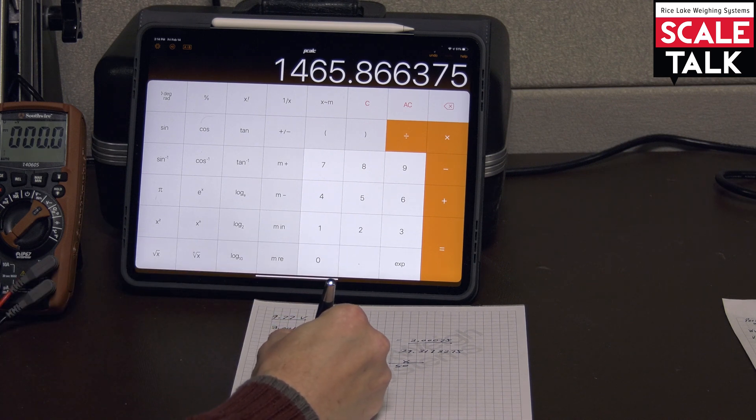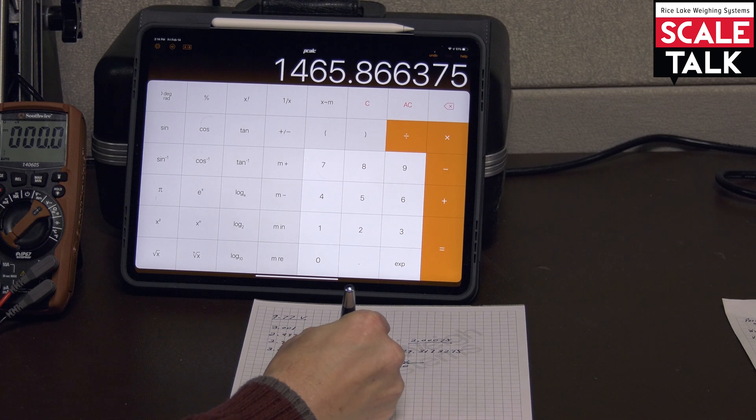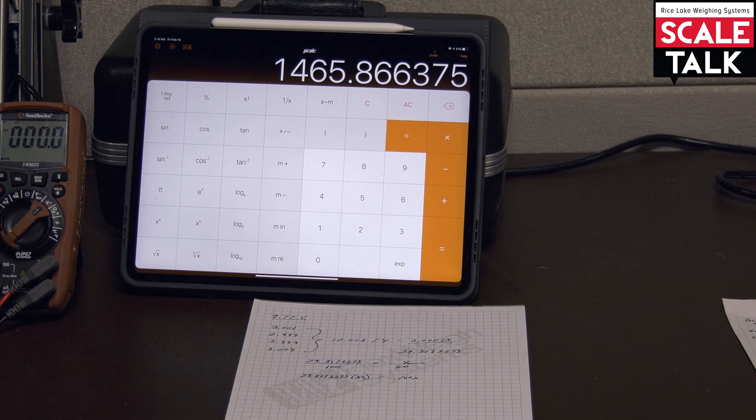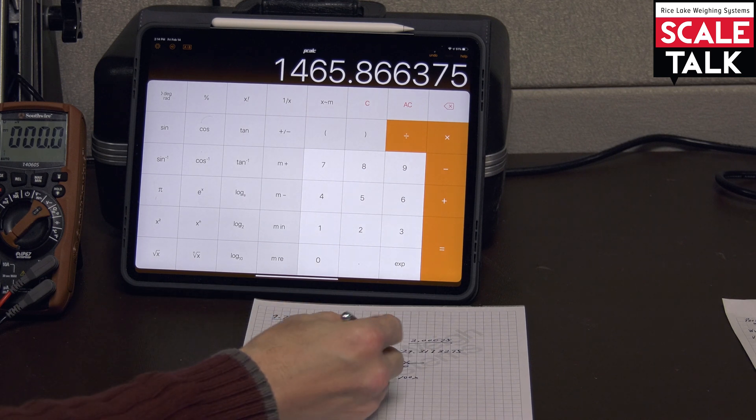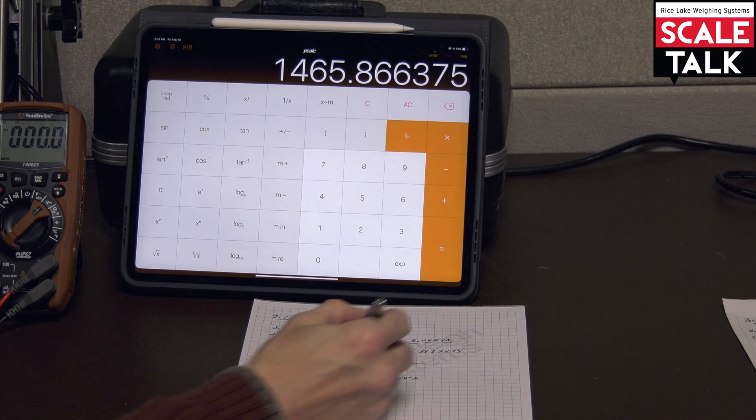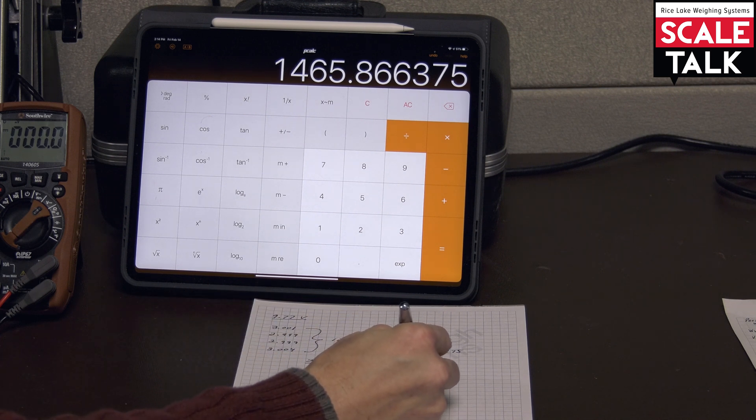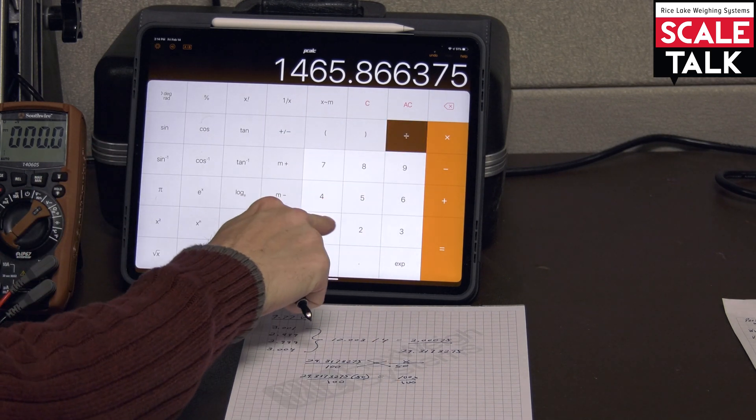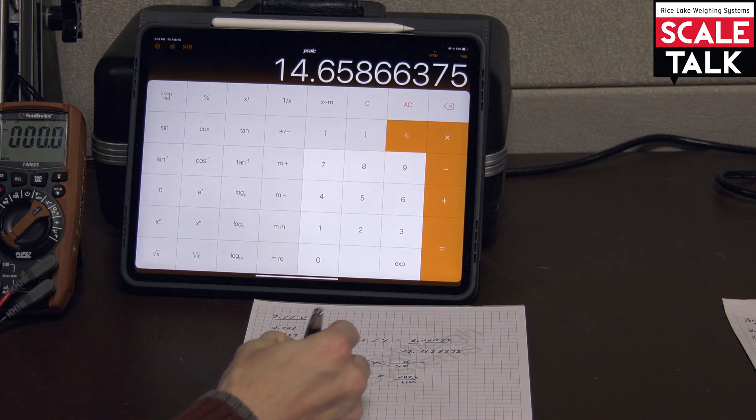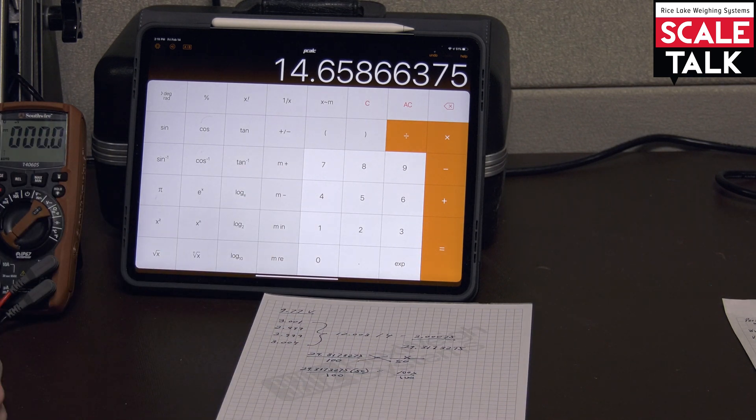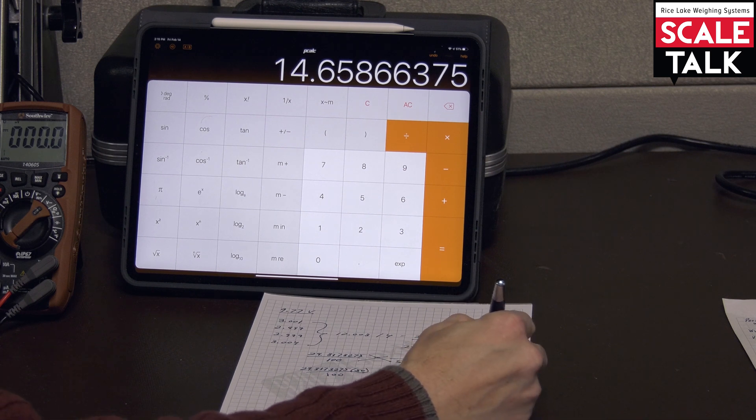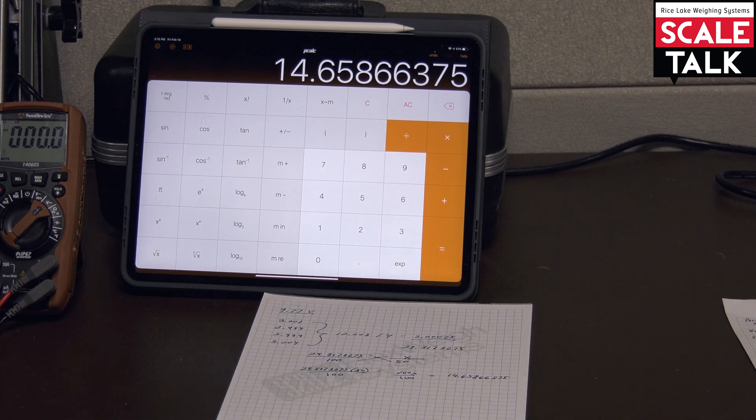And it gives us this value. So what we're doing here, we write this out. That's our cross multiplication. We take these two this cross way, multiply by these two this cross way, and they're equal to one another. So now I'm going to divide both sides by 100. So this answer gets divided by 100. And so this lets me know that at 50 pounds, which is what I'm setting as my span, that needs to be equal to 14.65866375 millivolts.